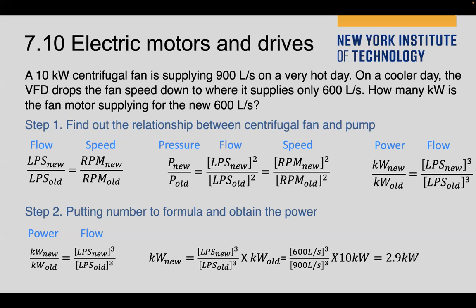First, the flow has a direct proportional relationship with the speed. Second, the pressure relates to flow and speed: the flow squared is directly proportional to the pressure. And the power takes flow cubed, or speed cubed, as the relationship.